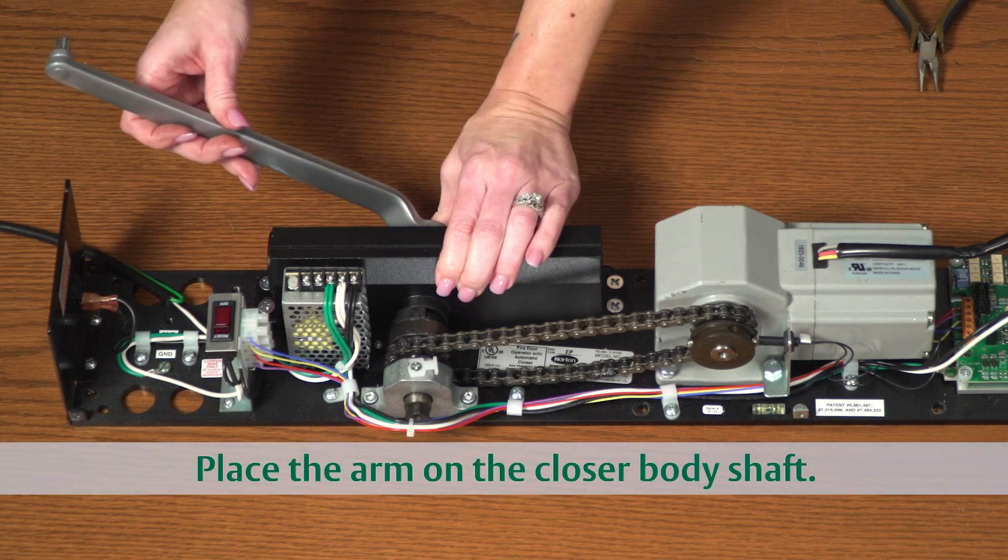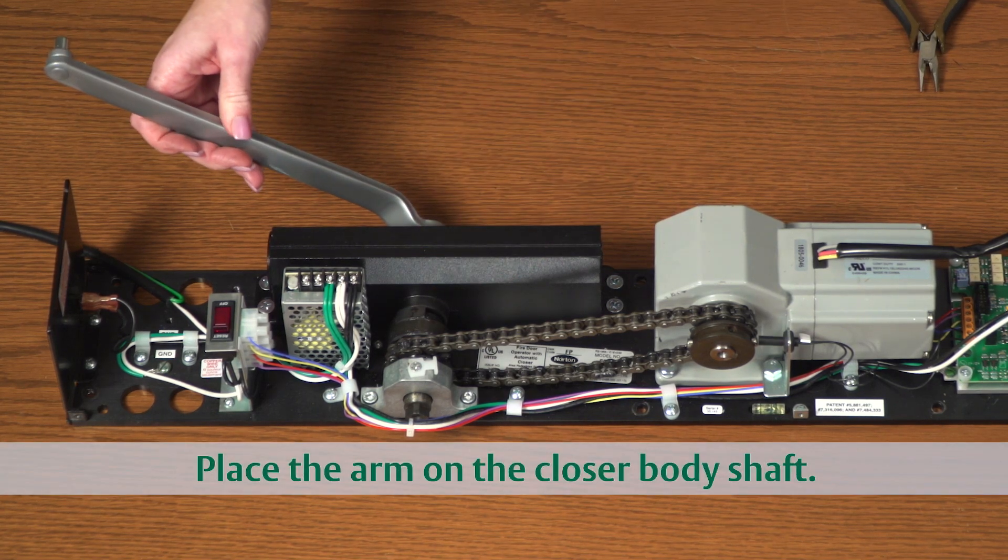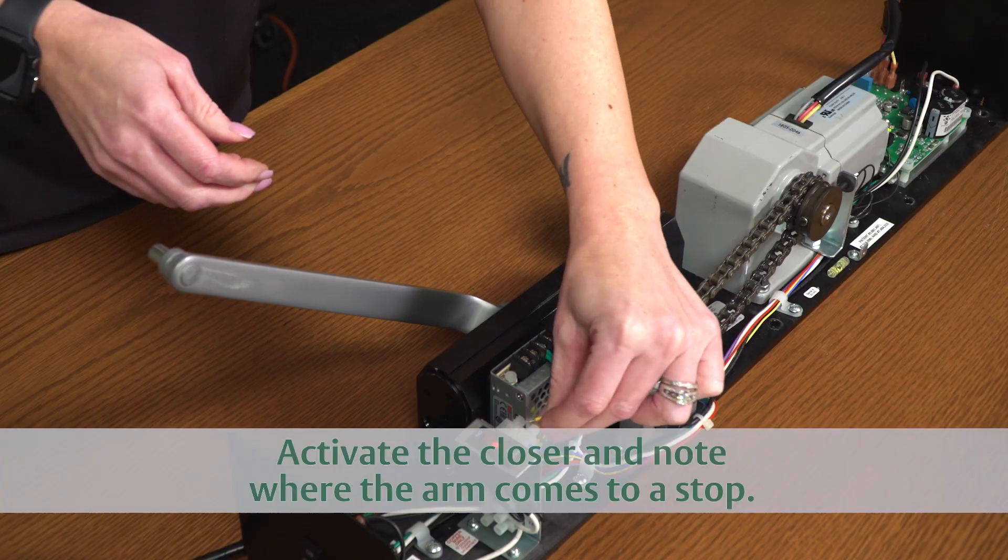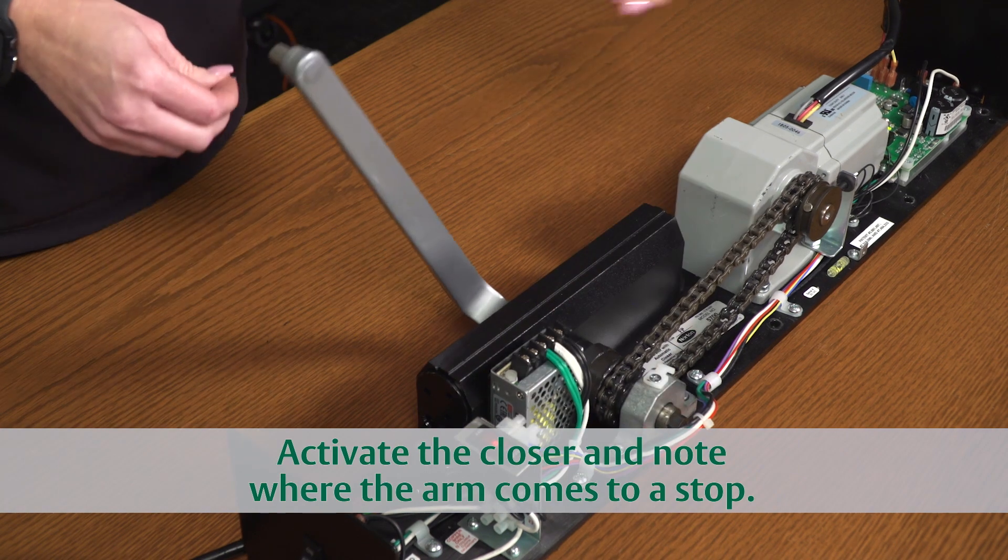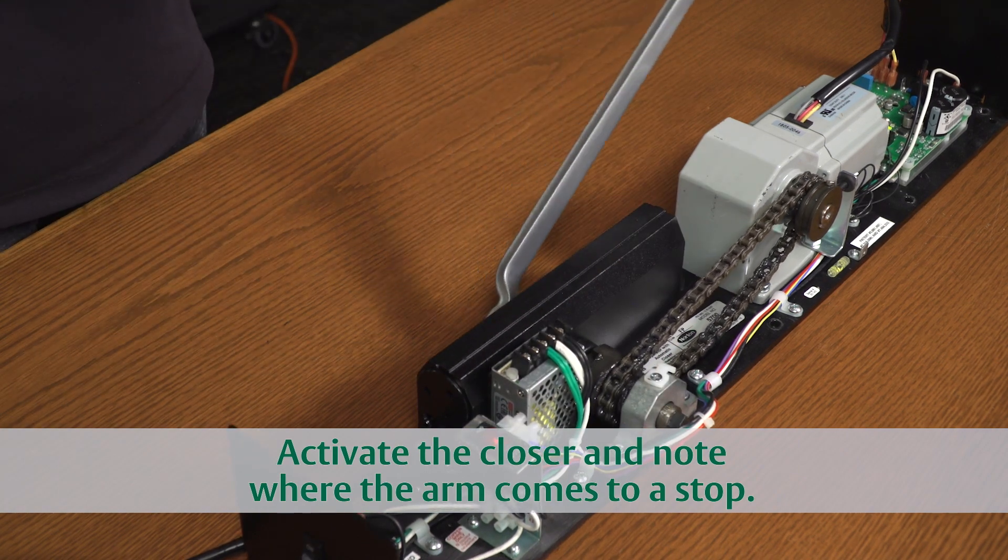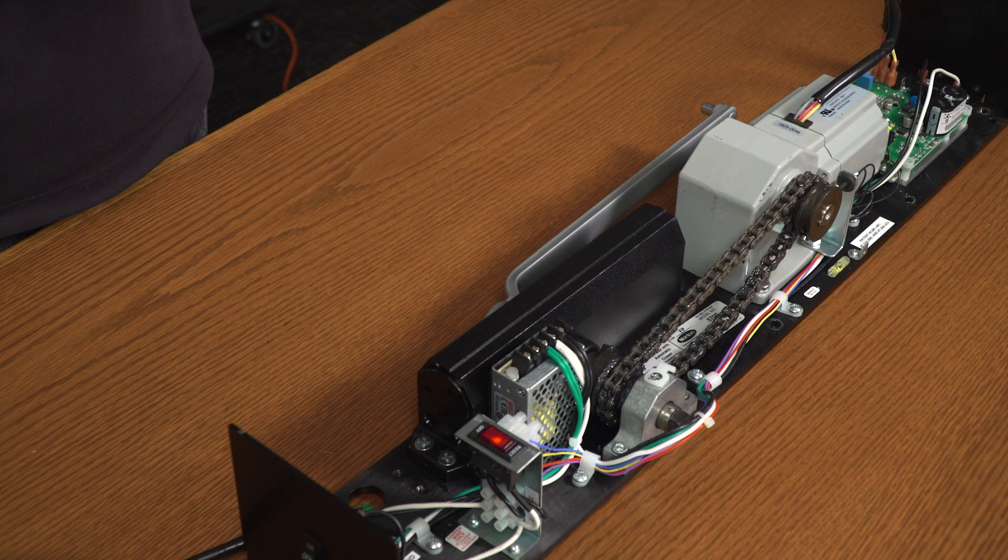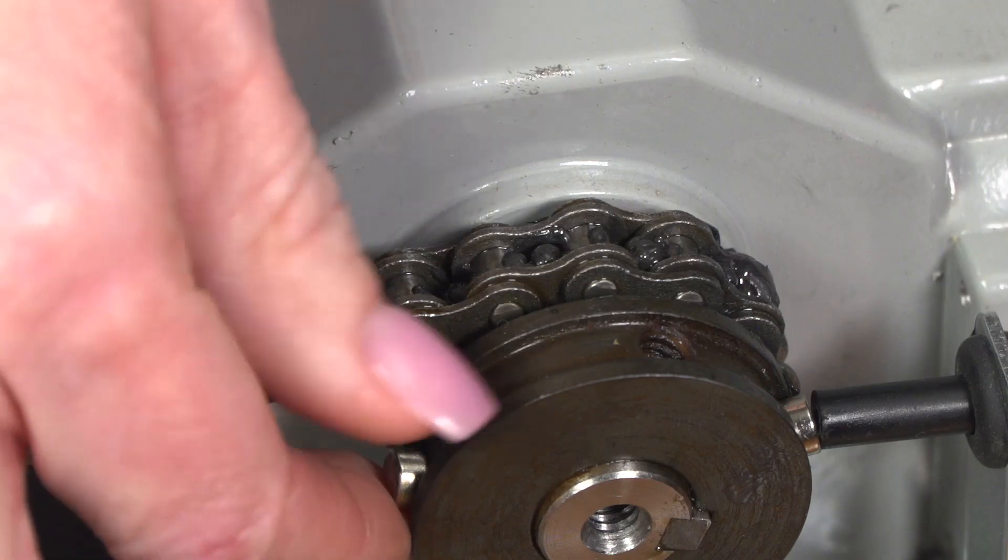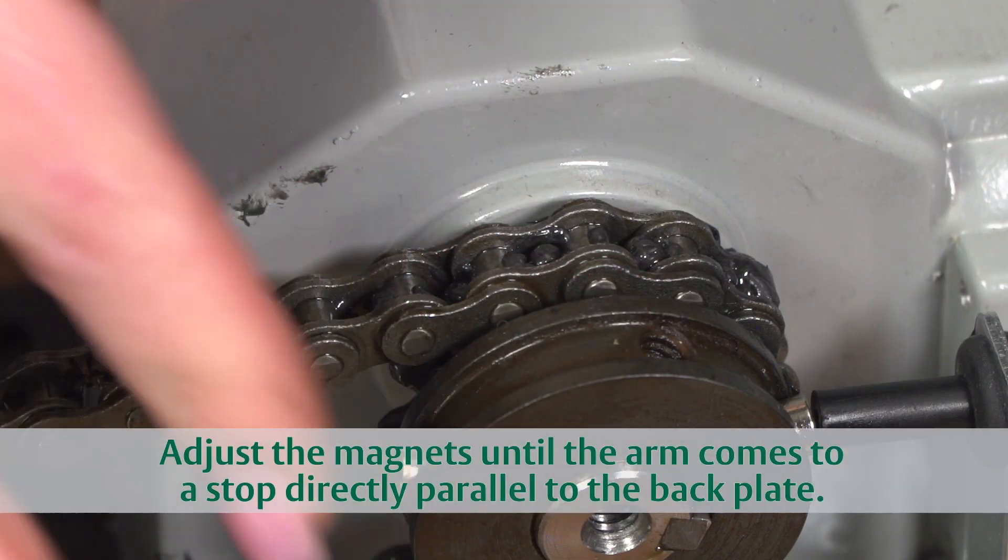To test the open and close parameters, place the arm on the closer body. Switch on the power and once again activate the operator. The arm should move to a position parallel to the operator. Adjust the magnets as needed to achieve the desired position.